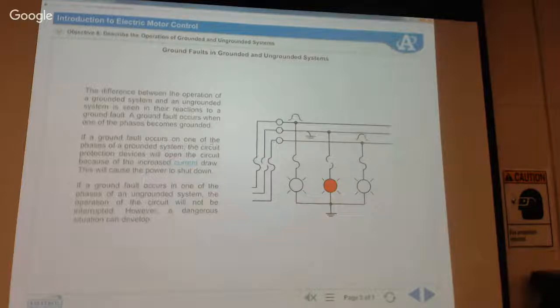So if a ground fault occurs on one of the phases of a grounded system, the circuit protection devices will open, and because of this, increased current will draw and will cause the system to shut down. Remember, these are the symbols right here on an ungrounded system. I guess you could say that, but on a three-phase system, you do have an earth ground. So here's our earth ground over here.